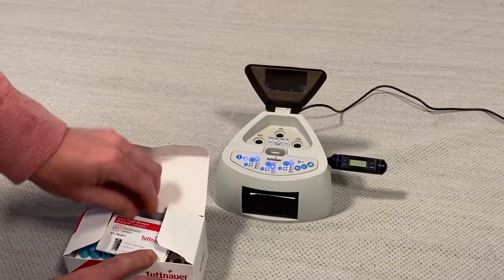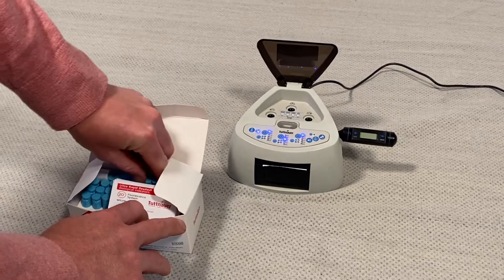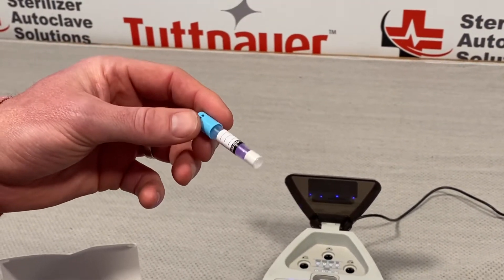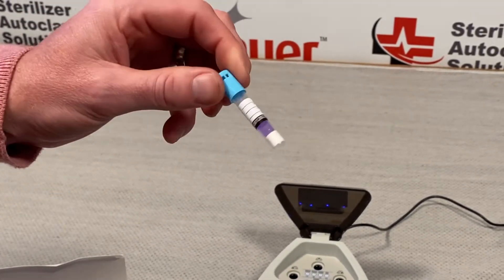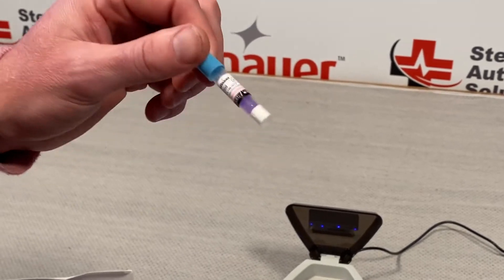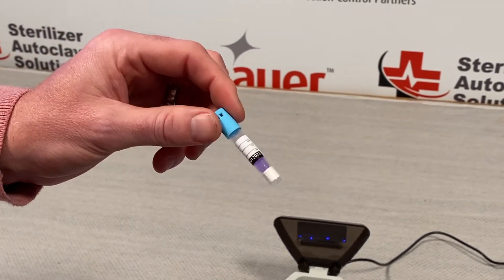So the first step is: once the indicator has been placed in your autoclave or sterilizer and has gone through the cycle, we're going to pull this out. There is live bacteria in a vial inside here. If the steam sterilizer did its work, that bacteria will be dead and it will give us the readout telling us that.